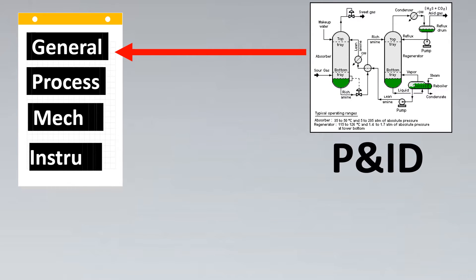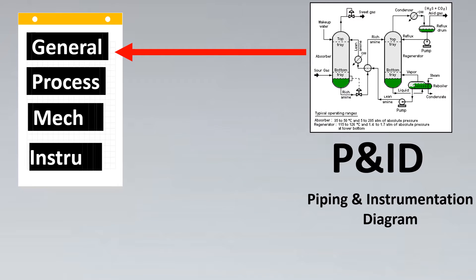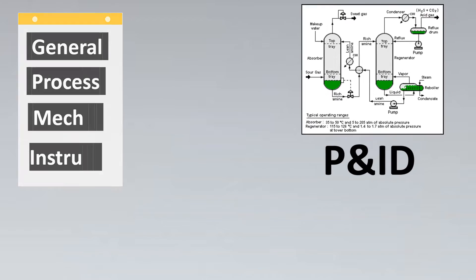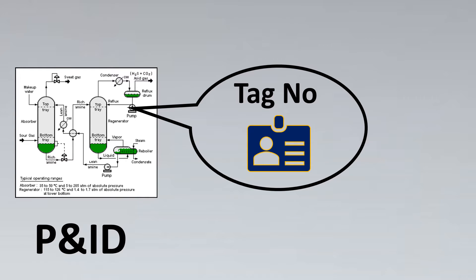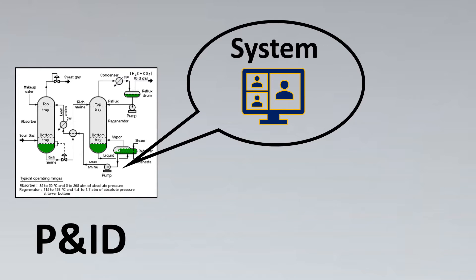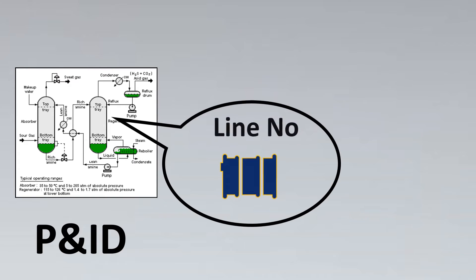For the general part, the input document — especially and predominantly — is the P&ID. From the P&ID we fill the tag number, which system the instrument is going to, which line number it's on or the equipment number, etc. So all the basic details are known from the P&ID, making it the first document needed to make a data sheet.